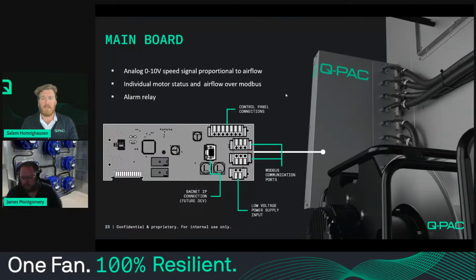Now you can actually just purchase a Q-PAC fan and run power and controls right to it. Currently all you need is 3-phase power and a 0 to 10 speed signal, and you can run the Q-PAC fan - it's going to take that 0 to 10 speed signal and distribute it out in parallel to all the other ECMs, so they all ramp up and down at the same speed currently.